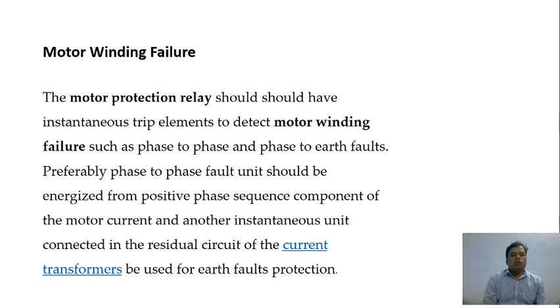The other condition is motor winding failure. The motor protection relay should have instantaneous trip elements to detect motor winding failure, such as phase to phase and phase to earth faults. We have learnt about faults, and here we are discussing phase to phase and phase to earth faults. What are these faults, and what is their relation with motor winding failure? We will have a look here. The relay should have instantaneous trip elements to detect that motor winding failure has occurred due to these two types of faults.